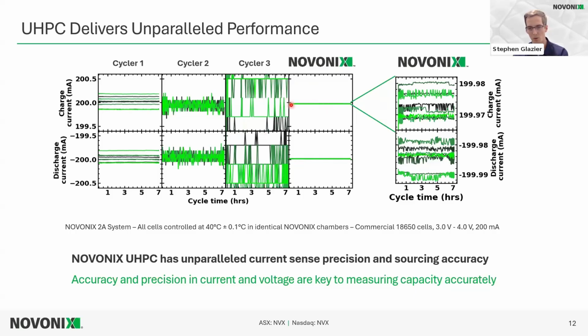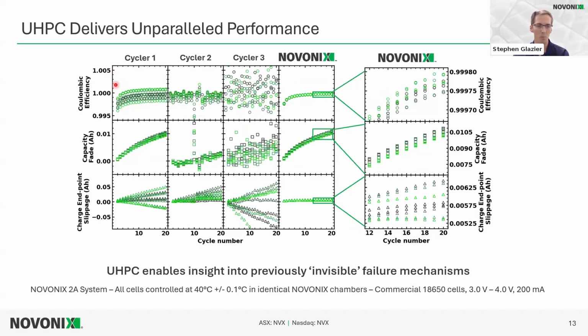Moving to the NOVONIX system, and just to prove this isn't just a flat line, we've blown up the axis here. When we translate this to cycle metrics that we use to interpret what's really going on when we're testing a cell, we can see that those raw data immediately translate to the full metrics. So here we've got really kind of clean traces of coulombic efficiency over time, but these identical cells put on this system all have different coulombic efficiency values. So again, good precision, but poor accuracy with these measurements. And this kind of propagates through with the other systems, cyclers as well.